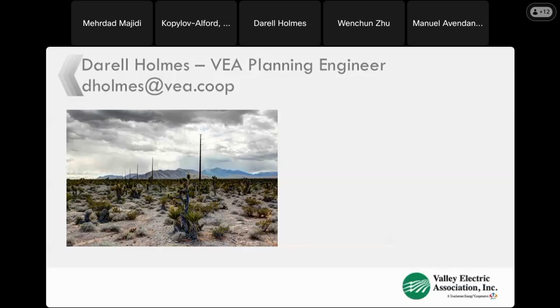Typically how the data center is being proposed is in 100 megawatt to 150 megawatt buildings, but it will be one site, and that could be spread over 2 or 3 customer 230 kV substations, then combine those and interconnect to the GridLiance substation. So there is some parsing of the load, 100, 150 megawatt data center buildings, and if it's 150 megawatts, that's 10 plus a little bit, so 11 buildings for this data center one.